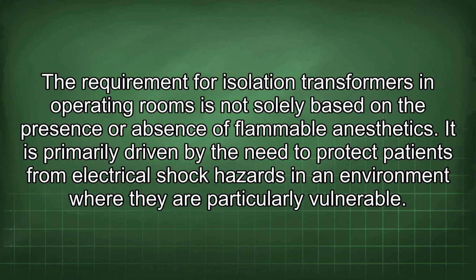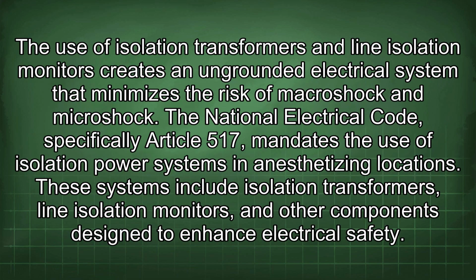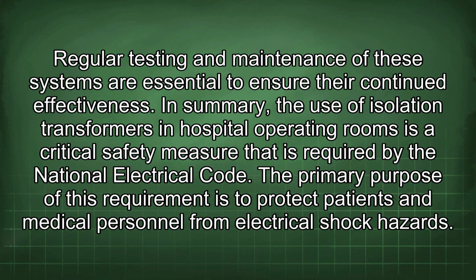The requirement for isolation transformers in operating rooms is not solely based on the presence or absence of flammable anesthetics. It is primarily driven by the need to protect patients from electrical shock hazards in an environment where they are particularly vulnerable. The use of isolation transformers and line isolation monitors creates an ungrounded electrical system that minimizes the risk of macroshock and microshock. The National Electrical Code, specifically Article 517, mandates the use of isolation power systems in anesthetizing locations. These systems include isolation transformers, line isolation monitors, and other components designed to enhance electrical safety. Regular testing and maintenance of these systems are essential to ensure their continued effectiveness.